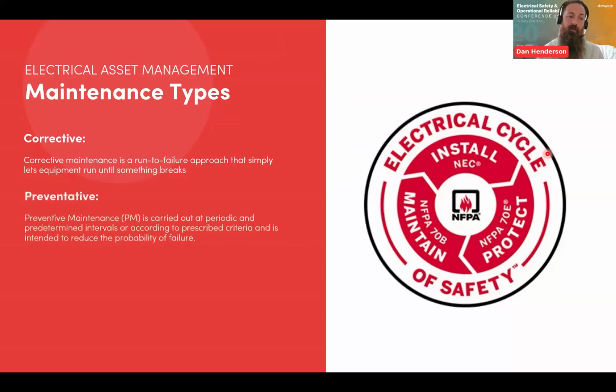We've got preventative. Preventative maintenance is carried out at periodic and predetermined intervals according to prescribed criteria, intended to reduce the probability of failure. That prescribed criteria might be a British standard like 6266, or an IEC standard, or NFPA 70B, as you can see there, which we're going to reference, or it might be the O&M manual. But it's in line with a prescriptive approach.